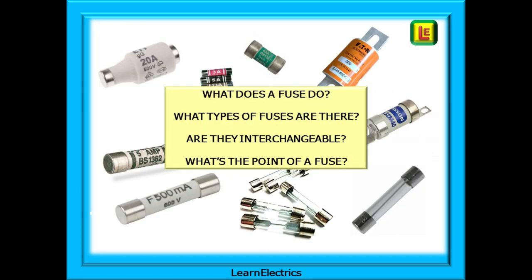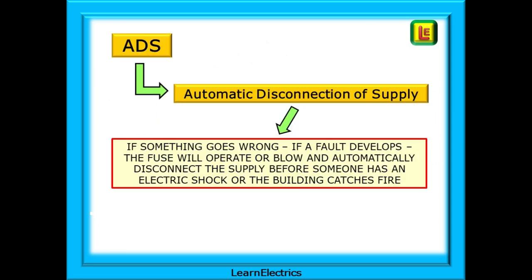Some frequent comments have included things like: what is a fuse, what does it do, what types of fuses are there and are they interchangeable, and just what is the point of a fuse — it's just a glass tube with a bit of wire, isn't it? When we install a fuse we are trying to achieve a certain response to faults in the circuit. We call this ADS, or Automatic Disconnection of Supply. If ADS has been correctly considered, then if something goes wrong in a circuit and a significant fault develops, the fuse will operate or blow and automatically disconnect the supply before someone has an electric shock or the building catches fire. That is ADS in a nutshell.